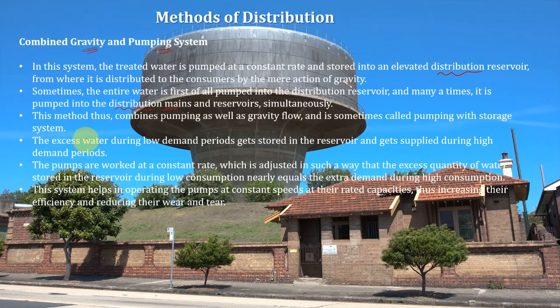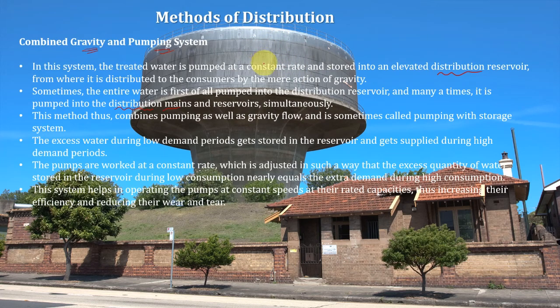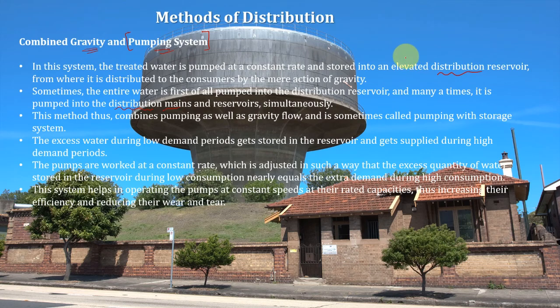This method combines pumping as well as gravity flow and is sometimes called the pumping with storage system. Excess water during low demand periods gets stored in the reservoir and supplied during high demand periods. During night time when demand is low, the pump operates at the same constant speed and same discharge, storing water. That same stored water is then used when demand is very high, so the pump does not have to vary its speed as it did in the pumping-only system.